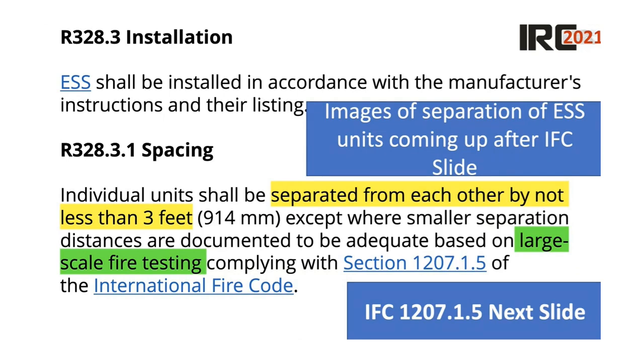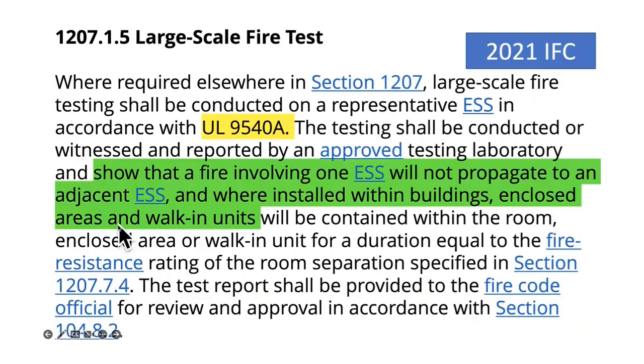And spacing. And so this is one of these things that the 9540A large scale fire testing, what I have in green, would make it so you don't have to do this spacing. I'm going to show some images on this too, separated from each other by 3 feet. That's what we're talking about. And so here's a little bit about that large scale fire testing. And it's a little bit controversial because the 9540A test is a pyromania test. It always catches fire, but they have to see at which point it catches fire where it won't propagate from one adjacent energy storage system cell to another. It won't just be like something that propagates.